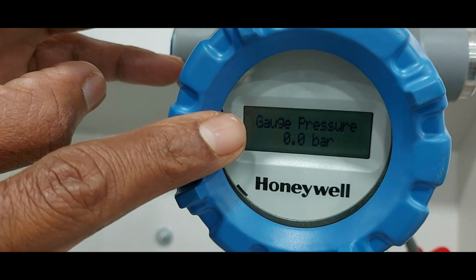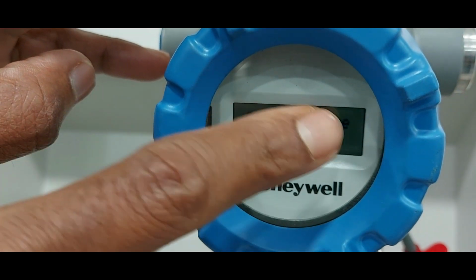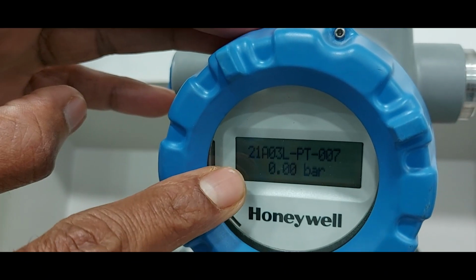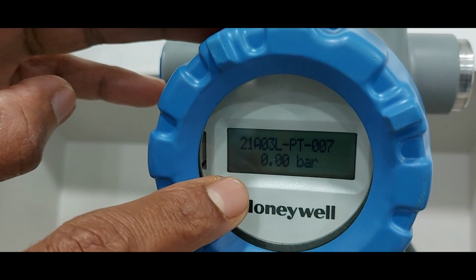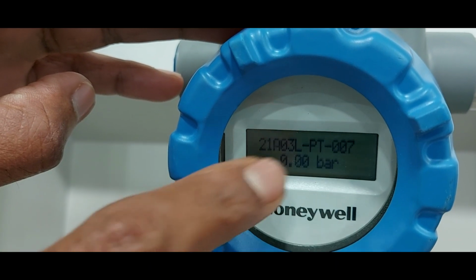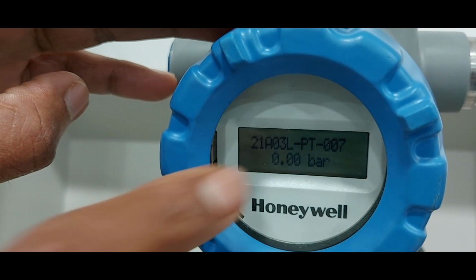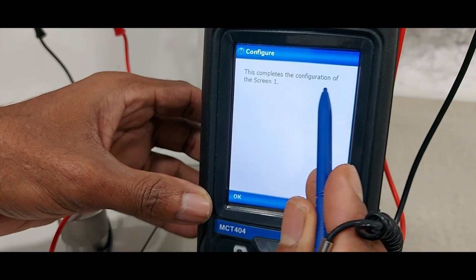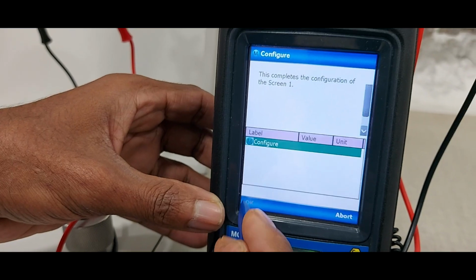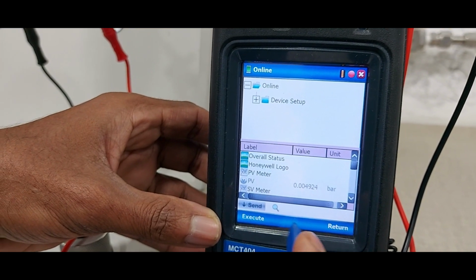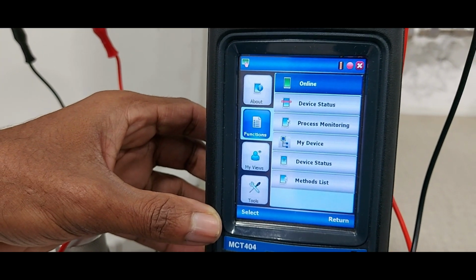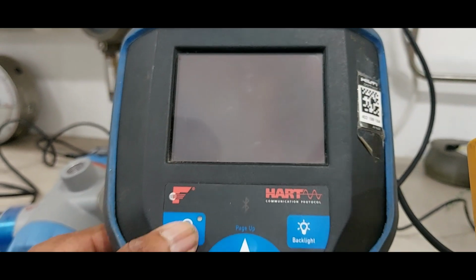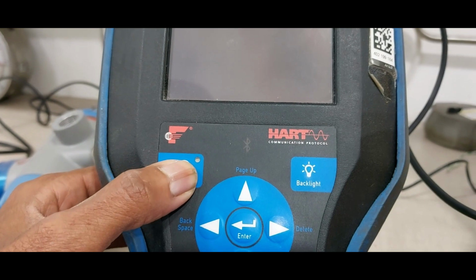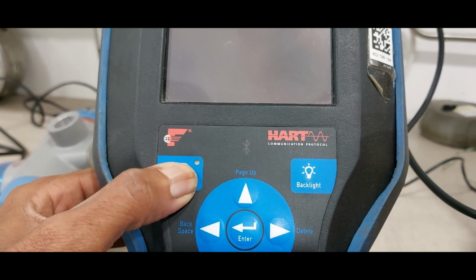Display is showing gauge pressure. Wait for 30 seconds. Display will be changed. Now display is changed. The tag number also showing. The decimal point also changed. Configuration is completed. Then OK. Okay, return. Next we are doing the calibration. Connect the field communicator and power on.